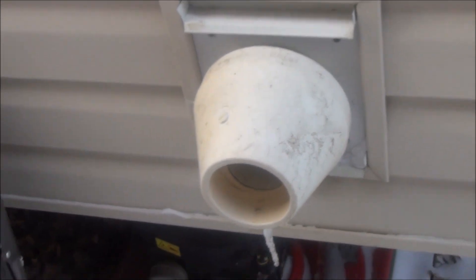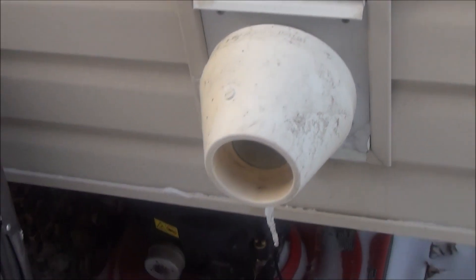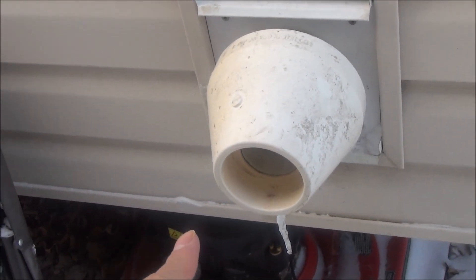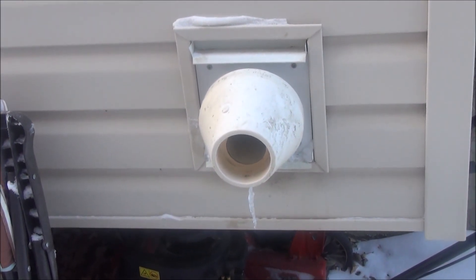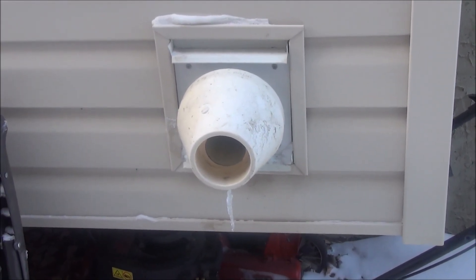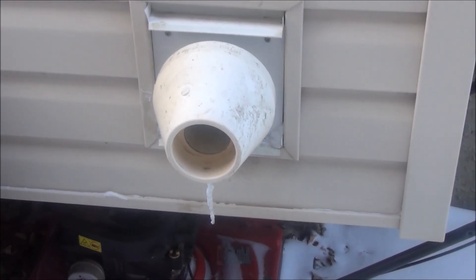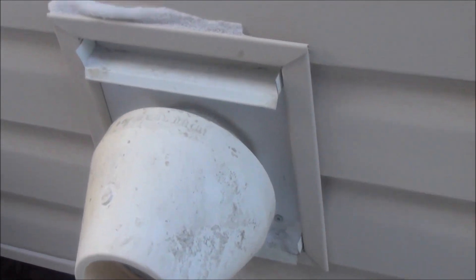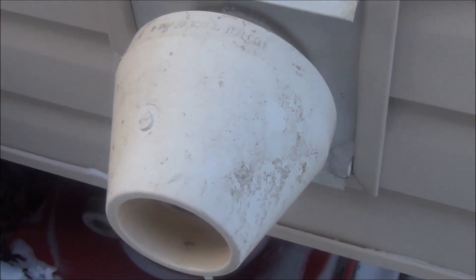That was so surprising to me, because the intake is hidden inside here, and I never paid attention — I didn't know this, so I didn't know it was blocked inside there. So now I took this lesson. I know I should come to check this every cold weather. This week is very, very cold — minus 30 for one week — and a lot of frost accumulated here and blocked the intake pipe.